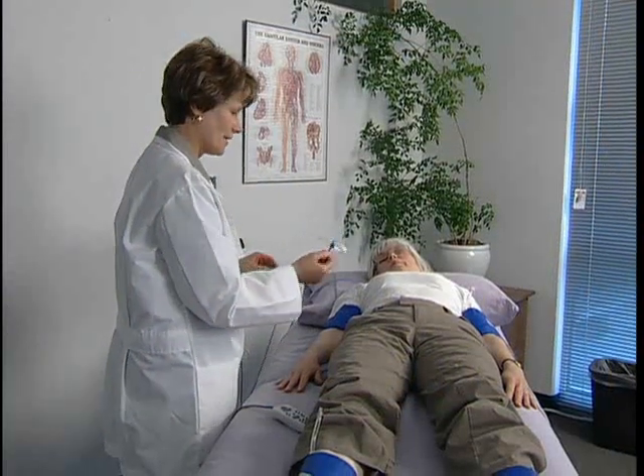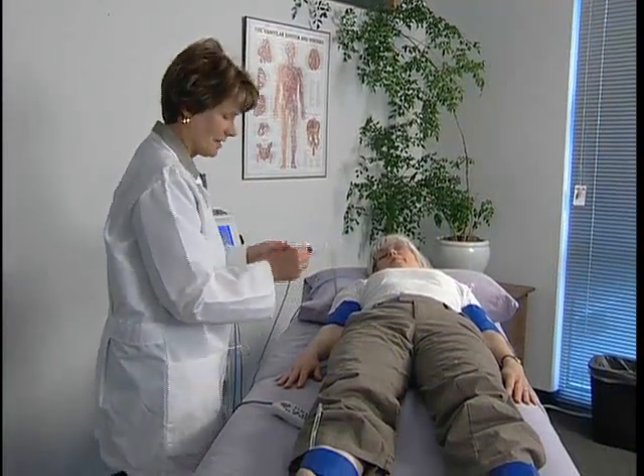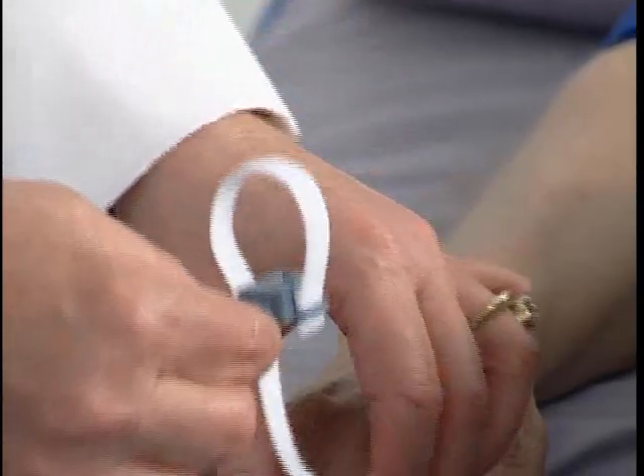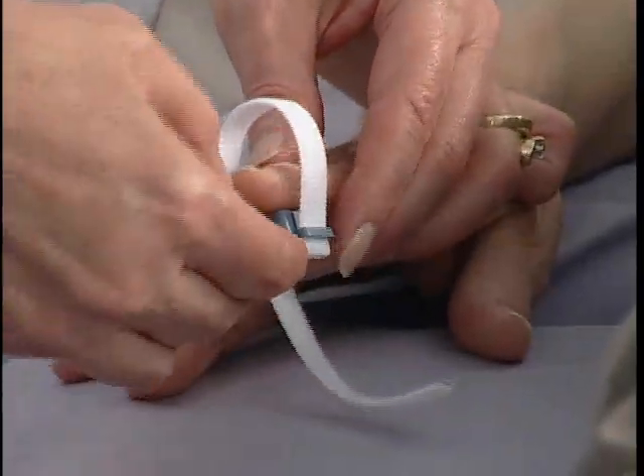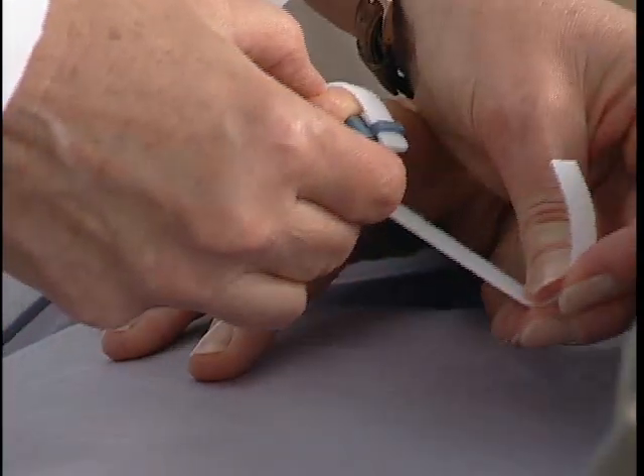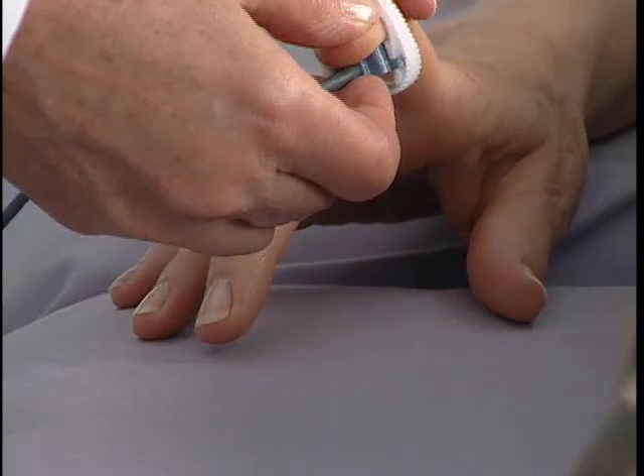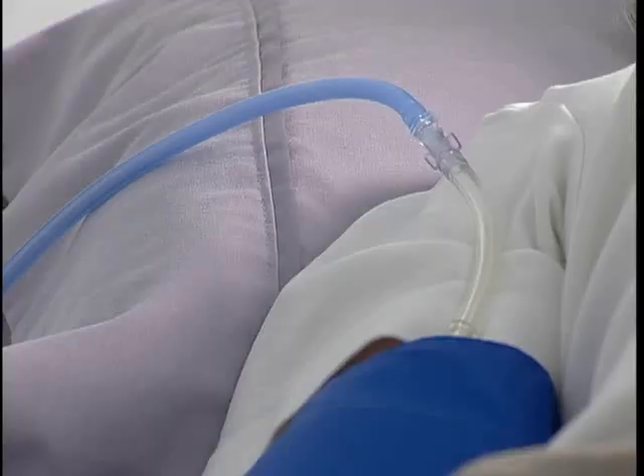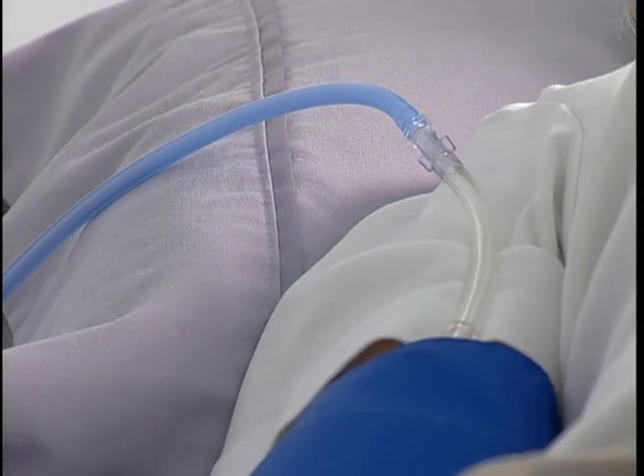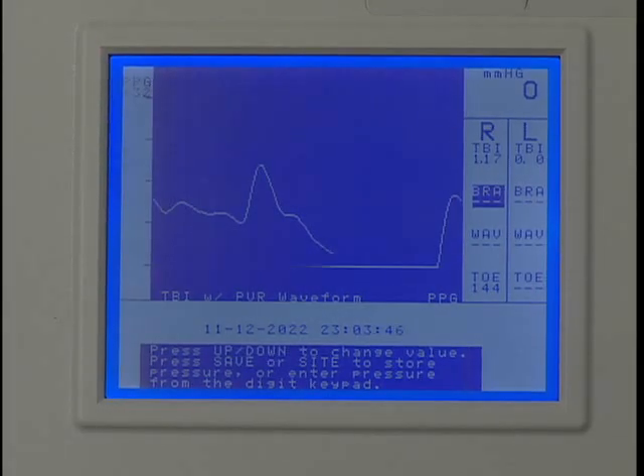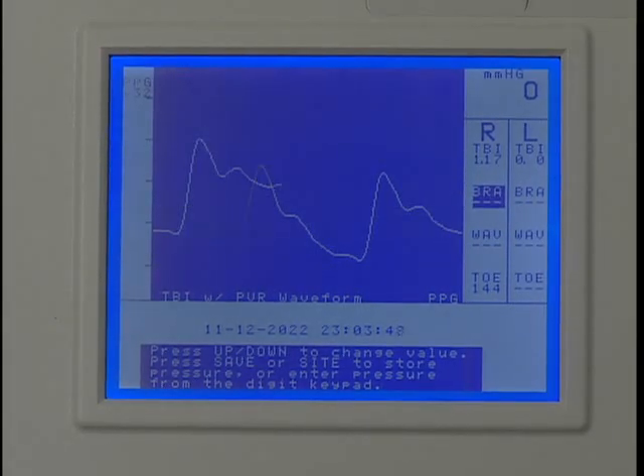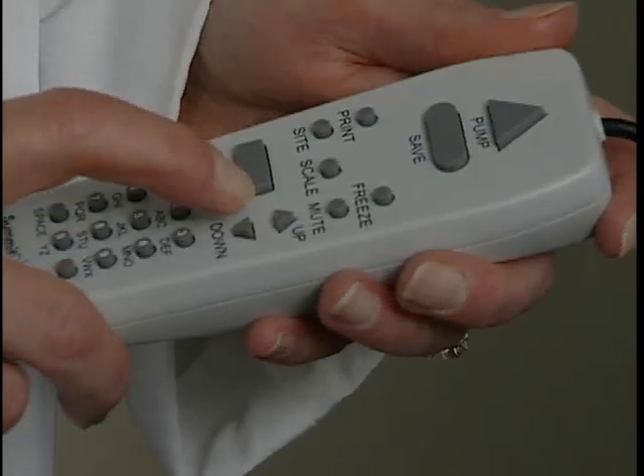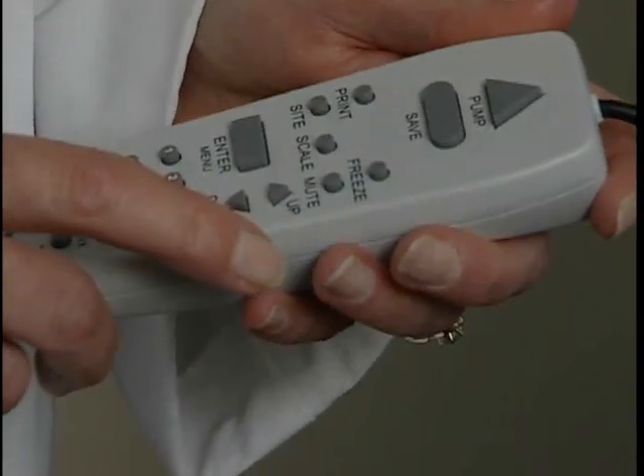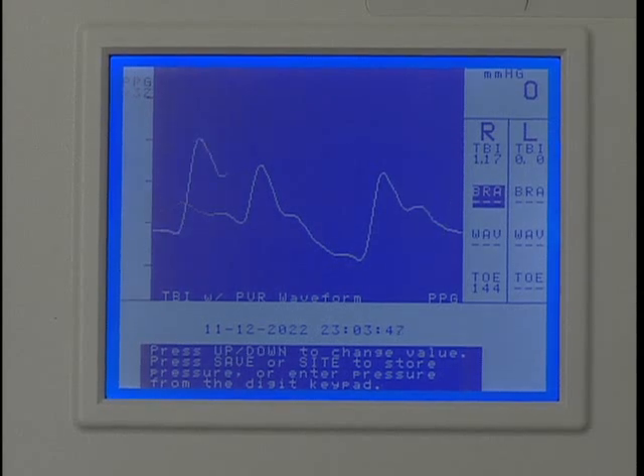Now we'll demonstrate using the PPG probe to obtain brachial pressures. Apply the PPG to the tip of the index finger as shown. Again, be sure the probe is snug but not too tight. Connect the pressure hose to the fitting on the right brachial cuff and wait a few seconds for the PPG waveform to stabilize after applying the probe. The patient must remain still. Press Scale to optimize the waveform on the display.